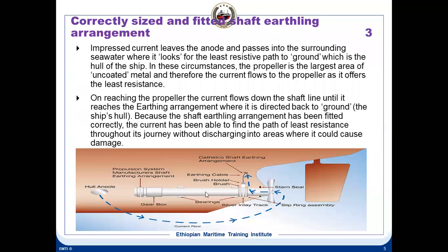You'll find, whenever the shaft grounding fails, it means the shaft and the earth potential exceeds 80 millivolt. Normally it is 80 millivolt. In most ships it is 80 millivolt. And whenever the millivolt increases, that means the grounding has failed. So whenever it exceeds 80 millivolt, it gives an alarm, the shaft grounding failure alarm.